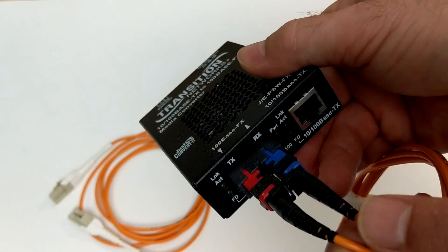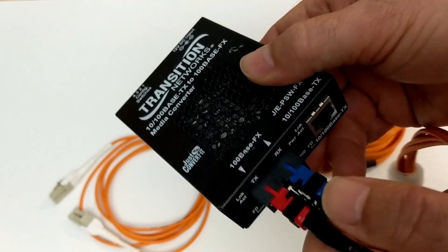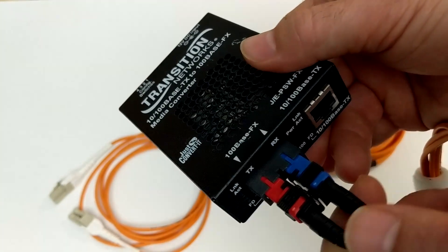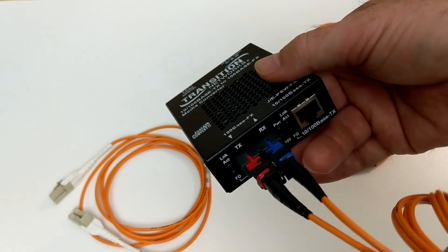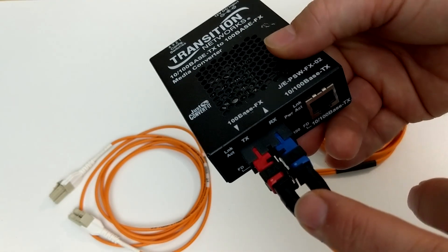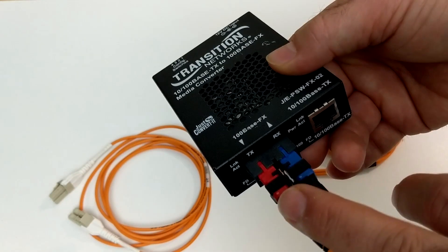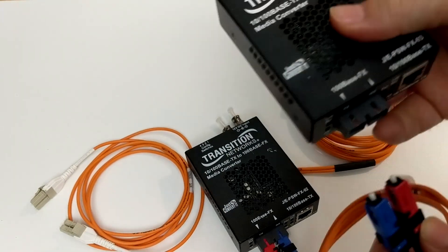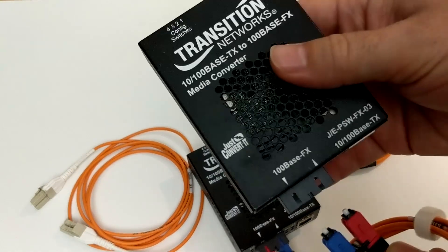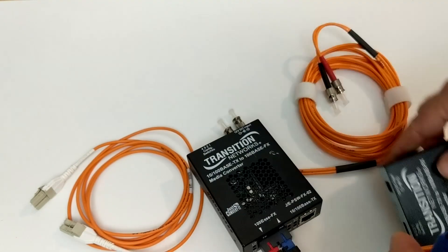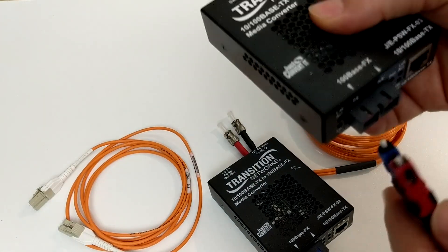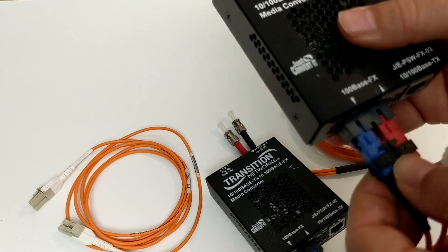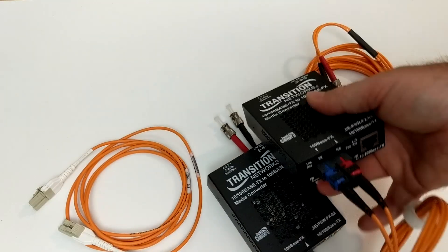All right, do you notice here how on this transceiver I've got a TX and a RX? Now, you're not always going to be lucky enough to have those designations on some of the equipment you're going to work with. But here's the key thing I want you to know. When you're connecting two transceivers together, which is typically the case, you're always going to want to have a crossover, meaning that whatever's coming out of transmit or TX needs to go into the RX on the other side. Does that make sense? So when light is being transmitted out of this port, it needs to go into the RX on the other port.